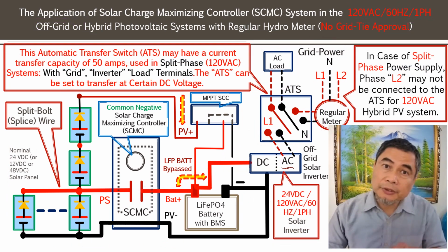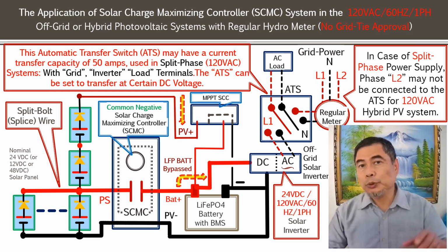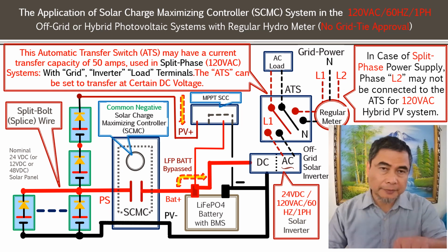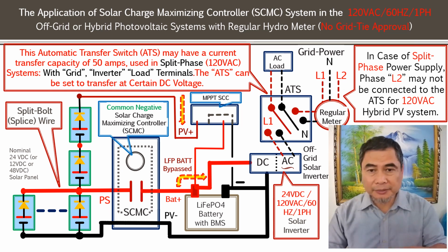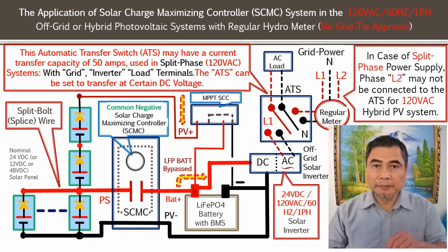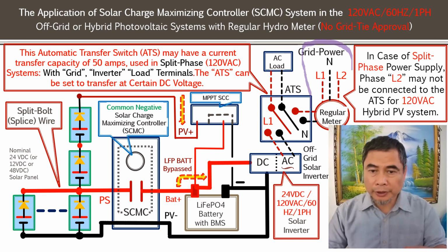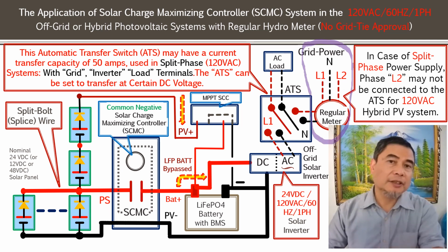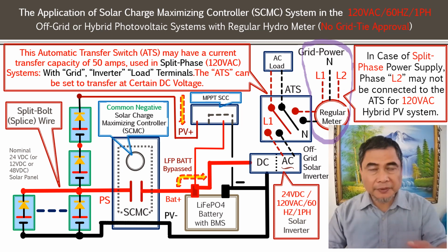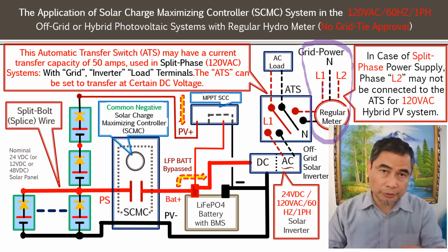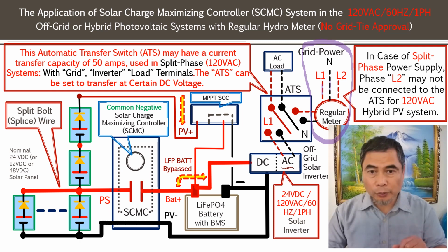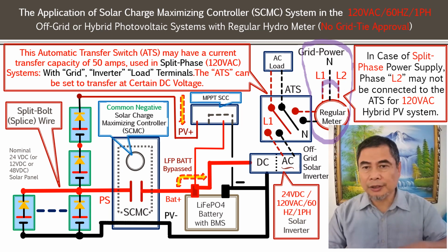This system looks identical to the system we just explained, a 220 system, 50 Hertz system. However, this system is actually a 60 Hertz system in North America. Grid power is 120/240. We call it a split phase system. It's 120 VAC if you connect L1 to neutral or L2 to neutral, that's 120. If you connect L1 and L2, that's 240. So this system is called a split phase.